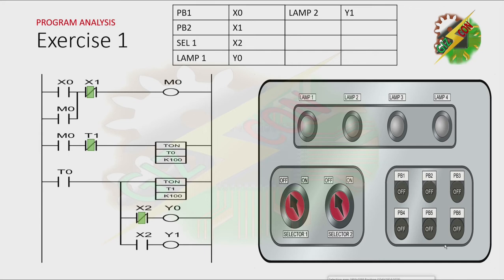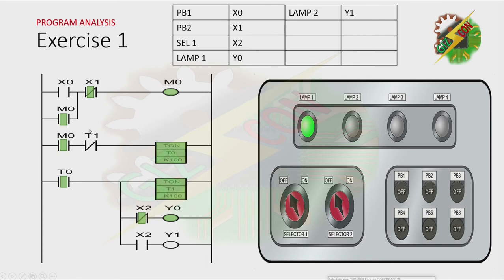Let's analyze the program first. This is my program. By pressing PB1, it will allow M0 to turn on and it will not turn off unless X1 is pressed. And because M0 here is on and T1 here is on also, timer 0 will start after 1 second. And because timer 0 is now on, Y0 will turn on. And after that, timer 1 will turn on after 1 second. And because T1 is a normally closed contact, it will turn off and that will cause T0 to turn off. To turn it off, we need to press X1.